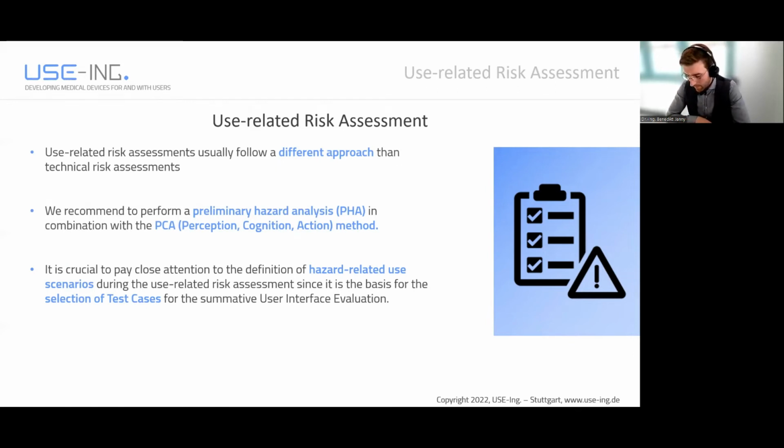So long story short, at this point within your usability engineering process, in strong combination and close collaboration with the risk management team, you decide what shall be used for your summative user interface usability evaluation. So it is really key to do everything right at this point, since it has a strong effect on everything that is coming up afterwards.